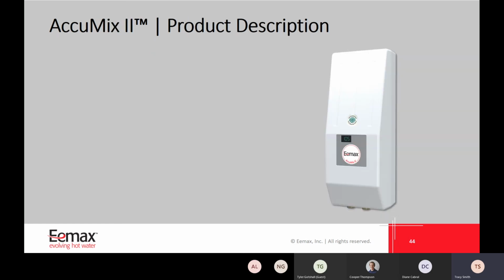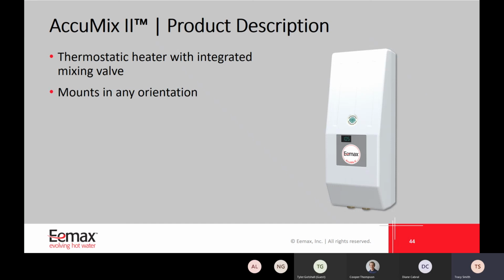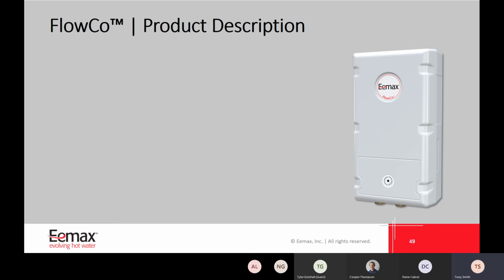Accumix 2 is a thermostatic heater with an integrated mixing valve. Why would you need that with a water heater? This is for any situation where you need to be code compliant to UPC 407.3. You can mount this unit in any orientation, and it's ideal for sensor or metering faucets in a public hand washing application.